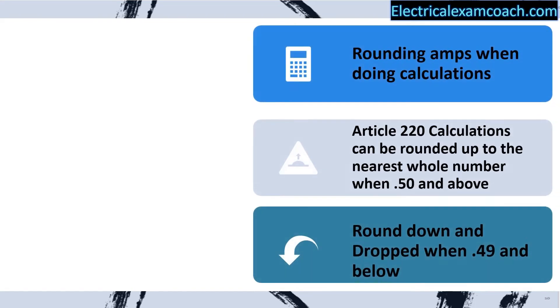In article 220 calculations, we're gonna be able to round up or down. We're gonna round up to the nearest whole number when it's 0.50 and above, and we're gonna round down and drop it when it's 0.49 or below. We're only gonna do it one time at the end of the calculation — you're not gonna be rounding up and down in between each piece, or you'll definitely end up with the wrong answer.